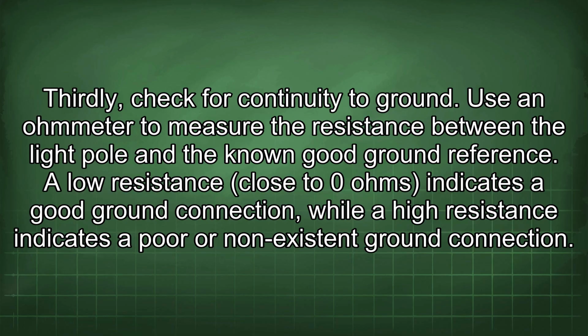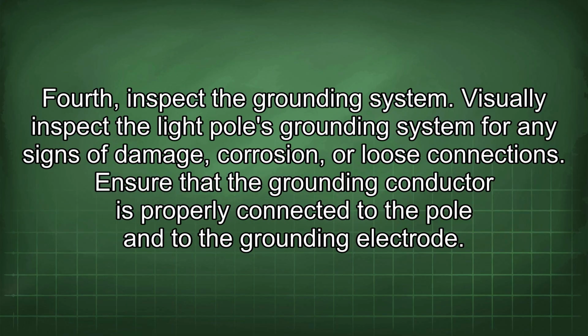Thirdly, check for continuity to ground. Use an ohmmeter to measure the resistance between the light pole and the known good ground reference. A low resistance close to 0 ohms indicates a good ground connection, while a high resistance indicates a poor or non-existent ground connection. Fourth, inspect the grounding system. Visually inspect the light pole's grounding system for any signs of damage, corrosion, or loose connection. Ensure that the grounding conductor is properly connected to the pole and to the grounding electrode.